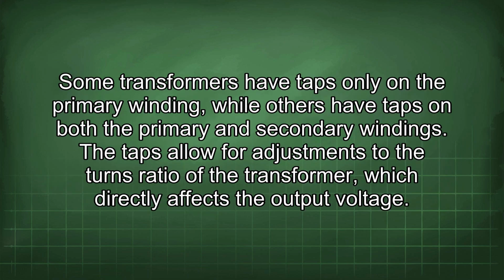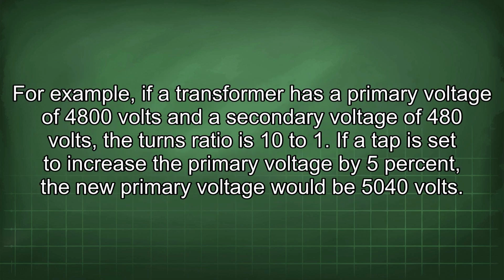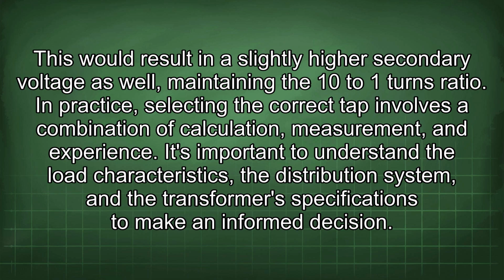Some transformers have taps only on the primary winding, while others have taps on both the primary and secondary windings. The taps allow for adjustments to the turns ratio of the transformer, which directly affects the output voltage. For example, if a transformer has a primary voltage of 4,800 volts and a secondary voltage of 480 volts, the turns ratio is 10:1. If a tap is set to increase the primary voltage by 5%, the new primary voltage would be 5,040 volts. This would result in a slightly higher secondary voltage as well, maintaining the 10:1 turns ratio.